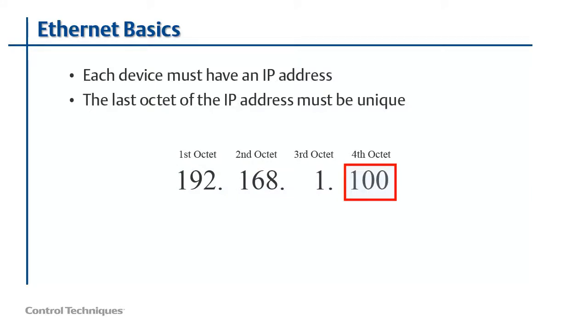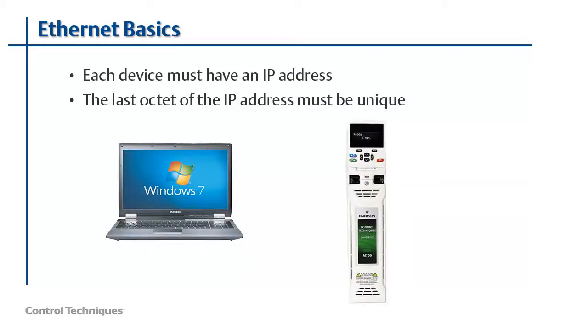A simple example would be a network that consists of a PC and a single Unidrive M700. The address of the drive is set to 192.168.1.100, and the address of the PC is set to 192.168.1.10. Valid choices for the last octet of the address are any number other than 0 or 255. Now let's have a look at how to configure an IP address in the drive.